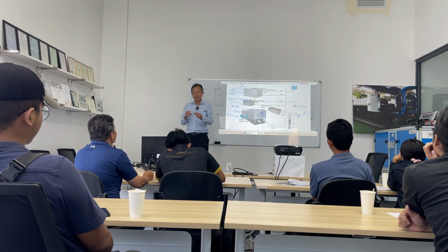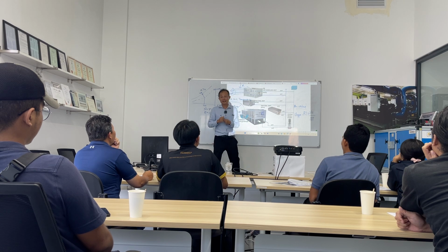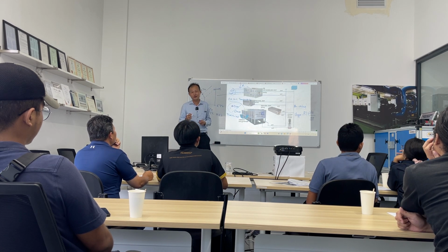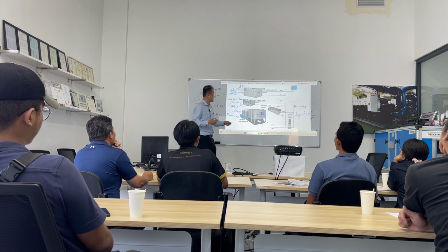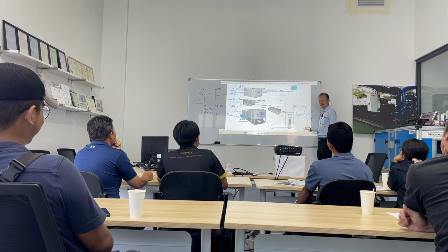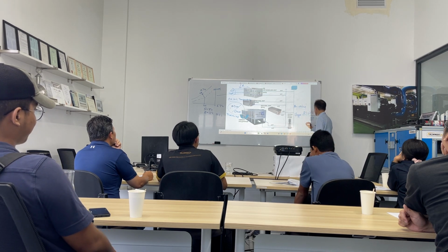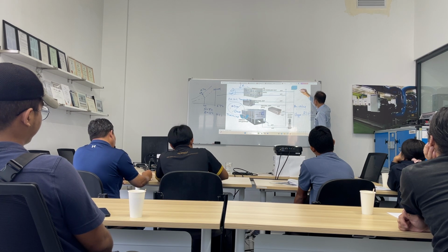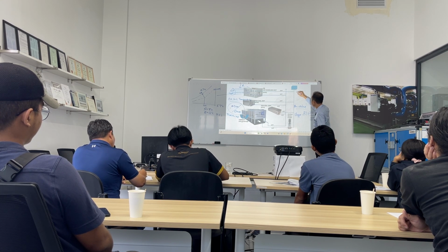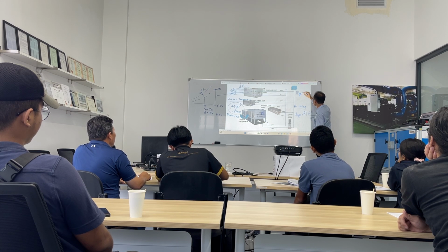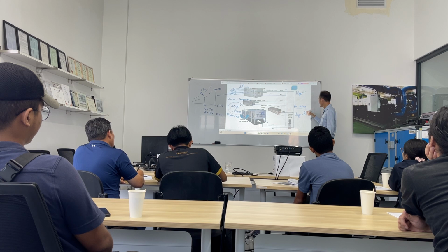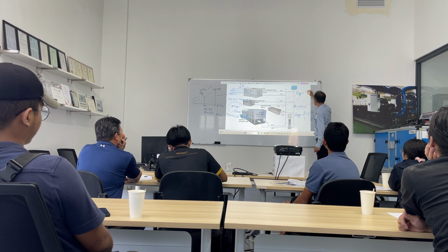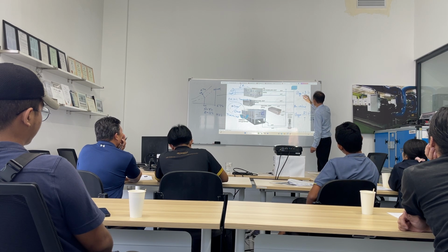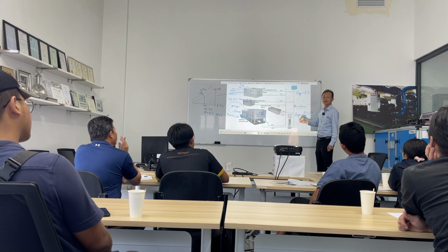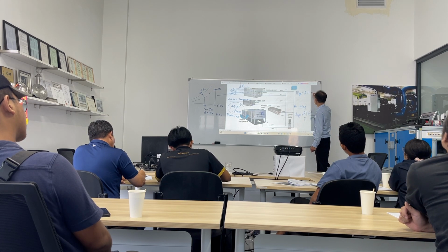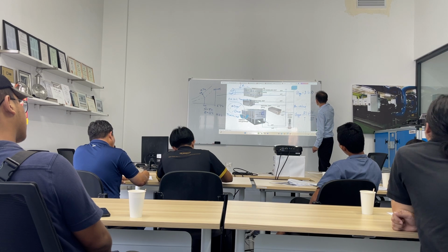The delta T here is 10. What is the delta T? Which one minus which one? This one minus this one, yes. Okay, so from here you can see 1 ton of cooling is equivalent to 2.4 US GPM. That means for 1 ton of cooling you need 2.4 US GPM.